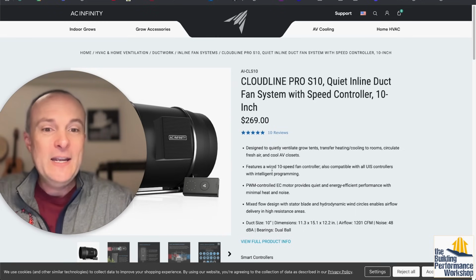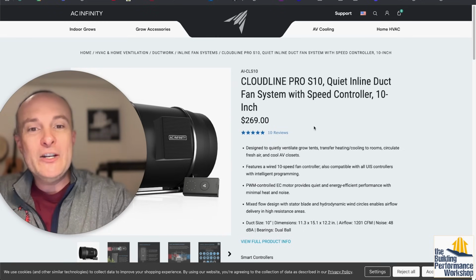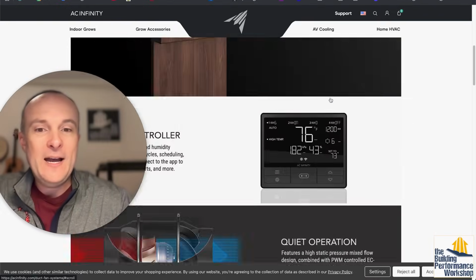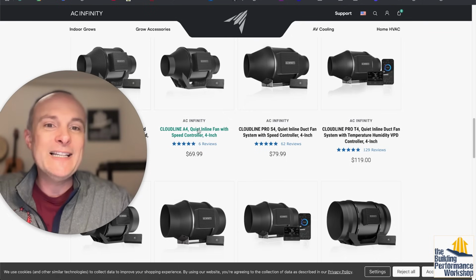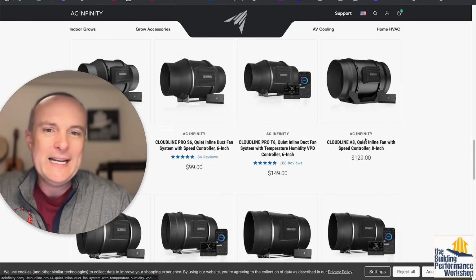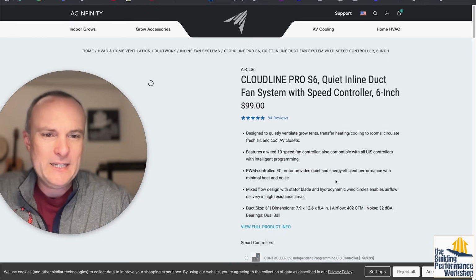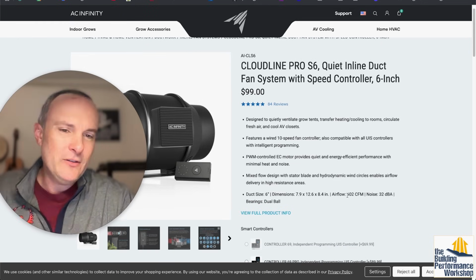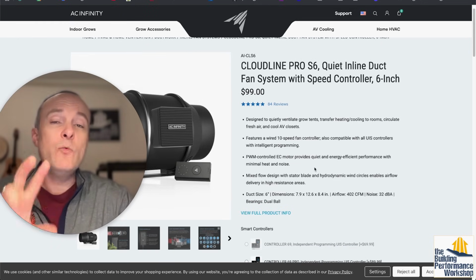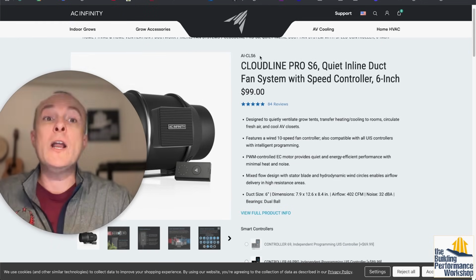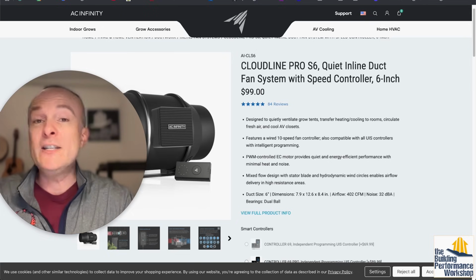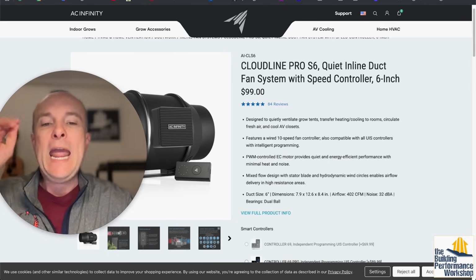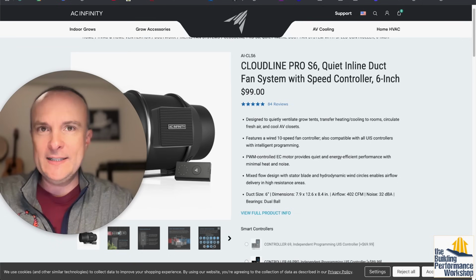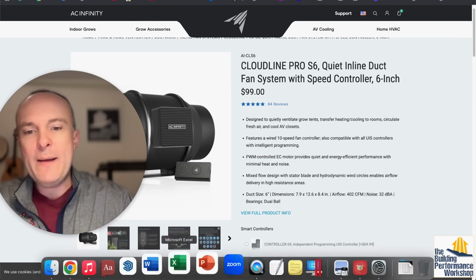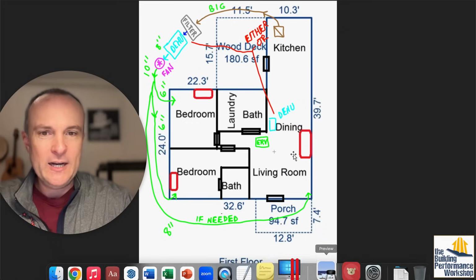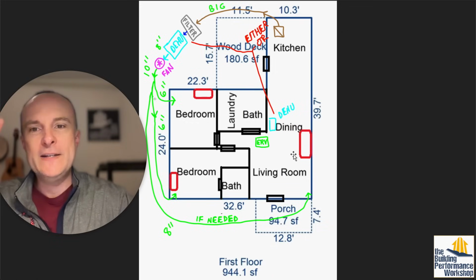That would be fine. What we're going to need to do then is shop for, in this setup, something that can deliver that. So if we were something like a 6-inch fan, let's just see, that should be somewhere around 300. Yeah, it can do 400. So let's do this one. We're not going to want to duct this with 6-inch though. We're going to want to upsize the ductwork so that we can get it to be as quiet as possible and so that we can get it to have as little resistance as possible. So that's why I'm upsizing it to what I'm talking about here with the 8-inch and the 6-inch.